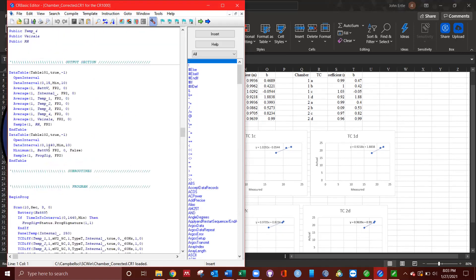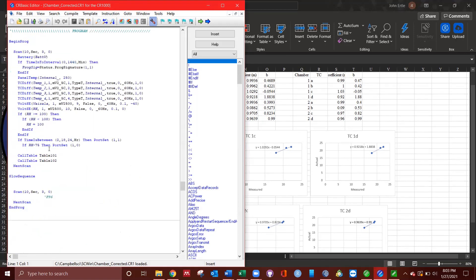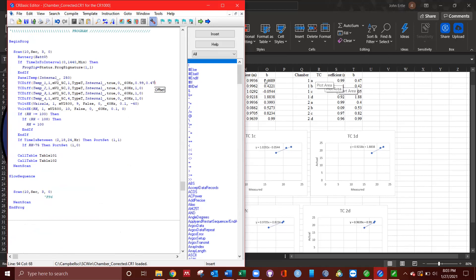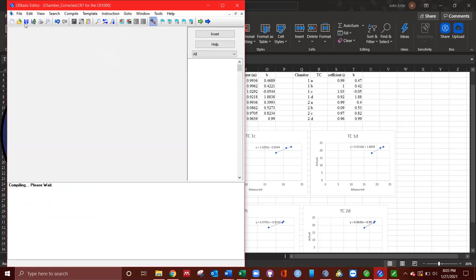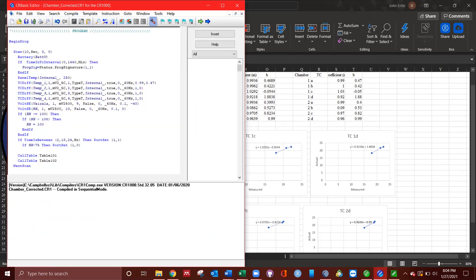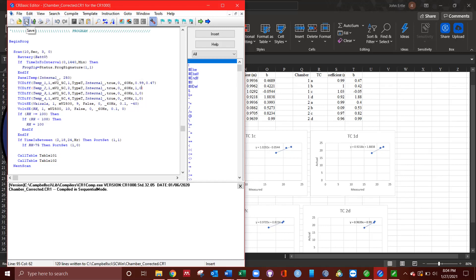What I want to do is go down here to the program writing. You see here, there's a one and a zero. The one is the M, the coefficient, and the B is the offset. So what I want to do is just go ahead and edit this 0.99 and 0.47 is my first thermocouple here. I want to do this all the way down. Since I have two chambers, I'll make a copy of this exact same program and I will do this twice. Once it's done, you hit compile and make sure that there's no errors in the program. Then I saved that. That's my corrected for thermocouple offset and coefficient. I'll do this for all four of those, copy it and do it for the other four.